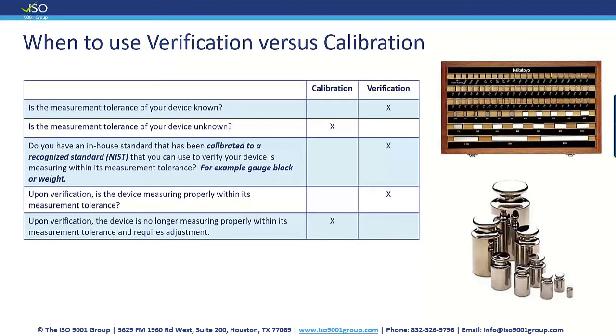What about this? Upon verification, the device is no longer measuring properly within its measurement tolerance, and it requires some adjustment. That's calibration. Then I need to send it out for calibration because when I tried to verify it, it was not reading within tolerance, and now there needs to be some adjustments. Now, you shouldn't be adjusting your equipment unless you are qualified to do that. If you are a calibration lab or you have internal expertise and the equipment to do that. But if it's reading properly and there's no adjustments necessary, that's verification.